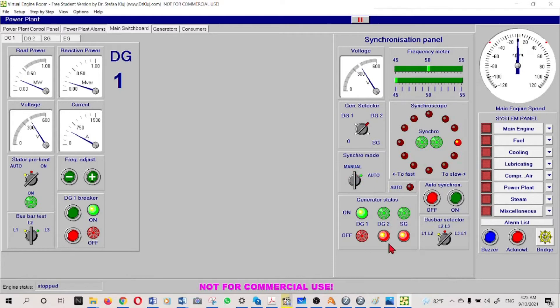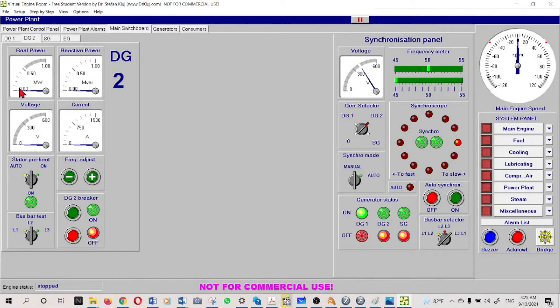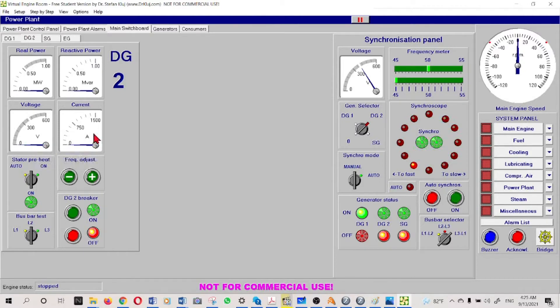The incoming generator is still not started so we cannot see any frequency value there. I will set automatic synchronization to manual because now we are going to do manual synchronization. Diesel generator number two is not started - we can see the breaker is off and there are no kilowatts, reactive power, amperes, or voltage - nothing.